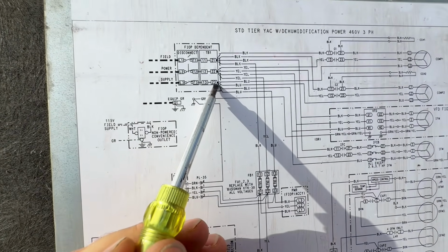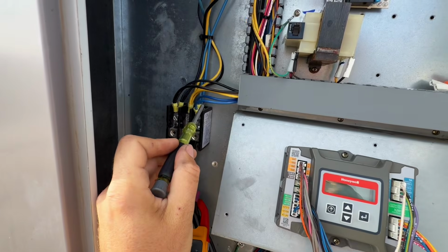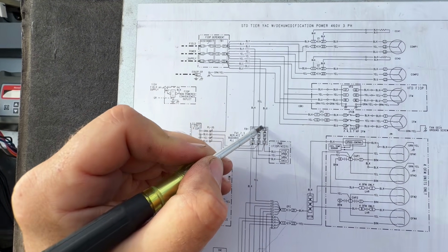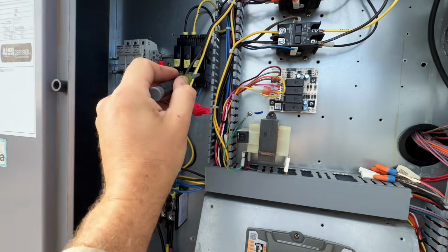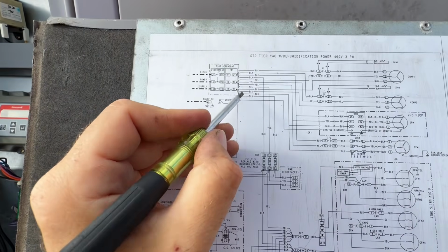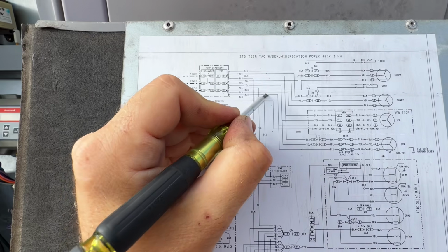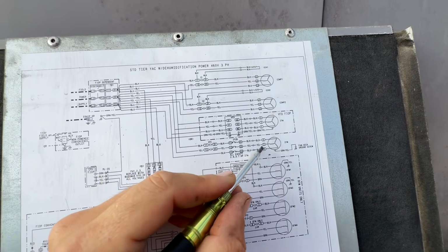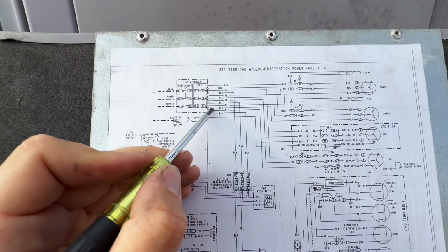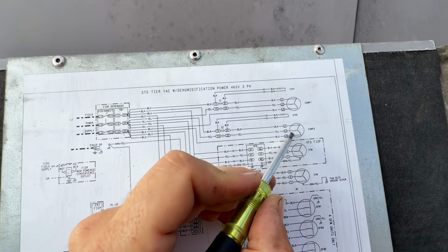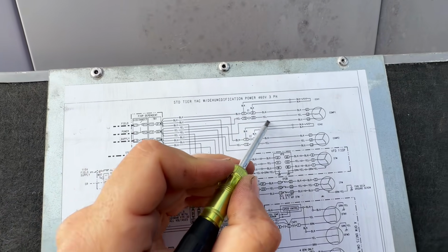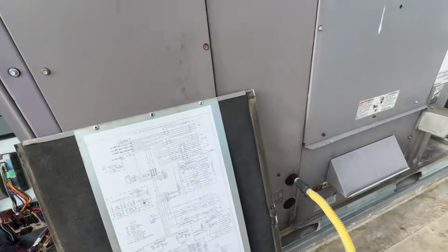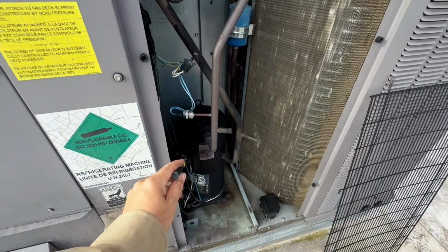And then you go here, you have blue, so you have 4 wires. You can see you have 4 wires, and you can look at these. So blue 1 goes over here, that will be our fuse, that's bypassed, so we don't have to worry about that. Then this one goes to your indoor fan motor, so this is always hot. And then this one goes to your compressor, and the last one probably goes to the last compressor. Exactly. So now you know where your wires go, and you can go to the components directly and simply troubleshoot at the component.